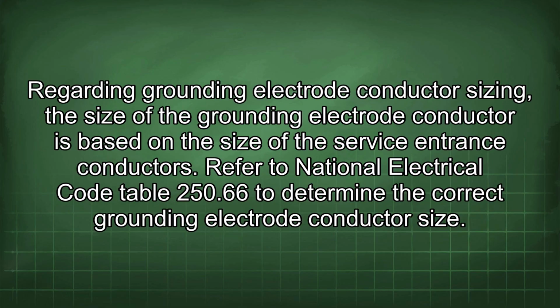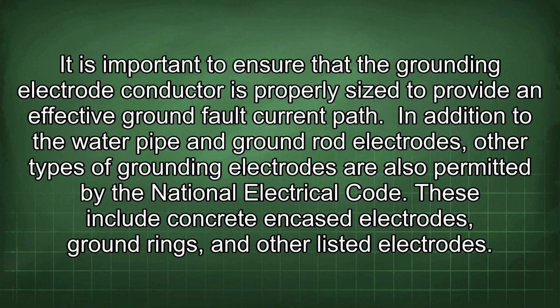Regarding grounding electrode conductor sizing, the size of the grounding electrode conductor is based on the size of the service entrance conductors. Refer to National Electrical Code Table 250.66 to determine the correct grounding electrode conductor size. It is important to ensure that the grounding electrode conductor is properly sized to provide an effective ground fault current path.